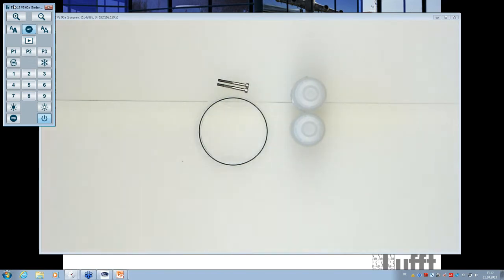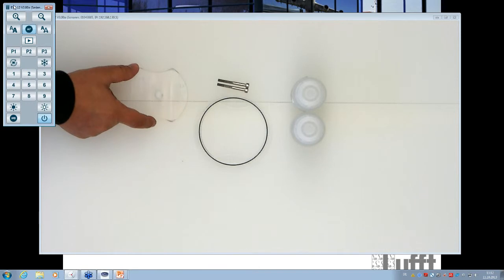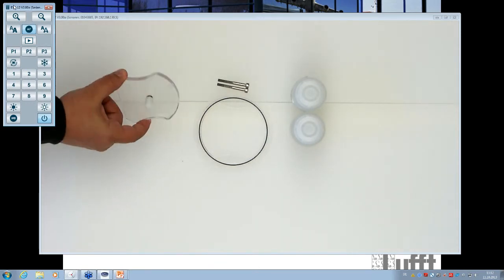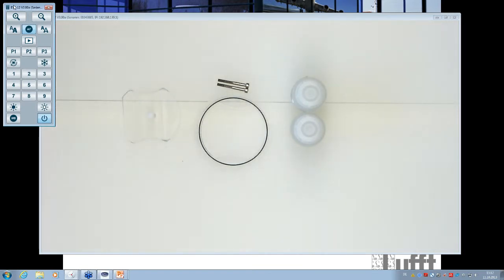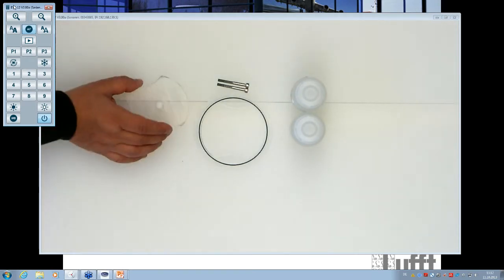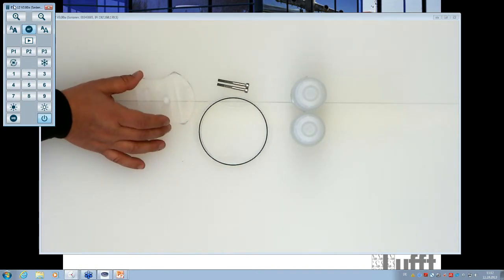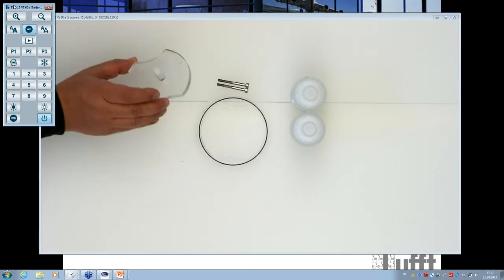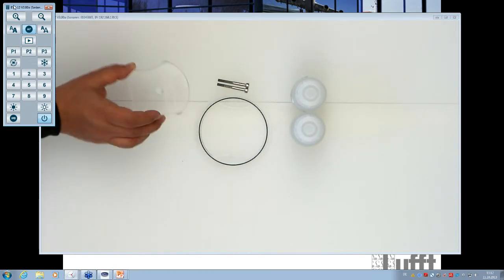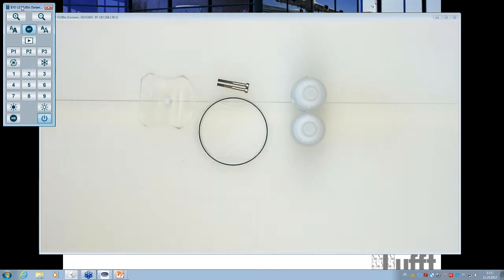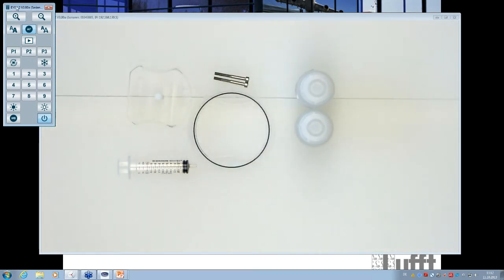Then in addition we have this plastic stamp. This stamp is used for the check of the freezing temperature. I told you that the freezing temperature measurement depends on the water film. To create a stable water film, we have this stamp, this insert, which will create a water film of 1 millimeter. We have to put that on the surface later. I will show you how to do it. And of course you will also have 2 syringes to fill in the water. These are the parts which are available if you order the IRS31 calibration kit.